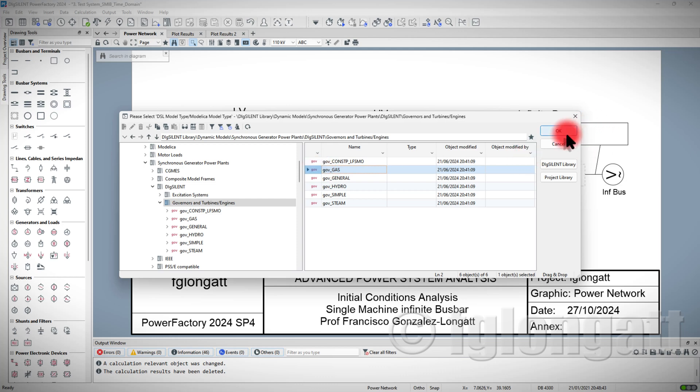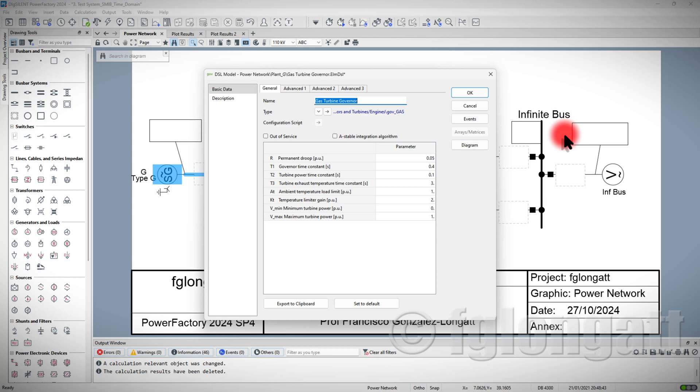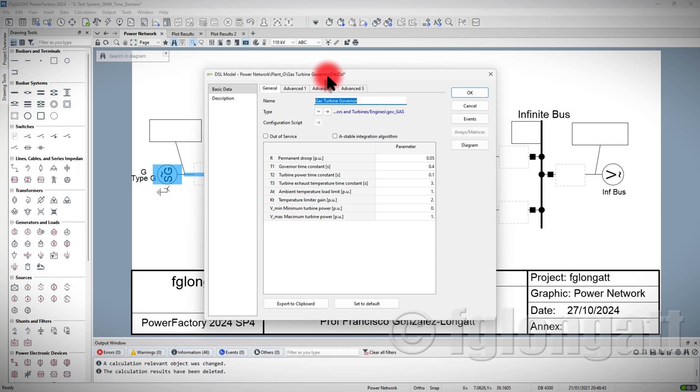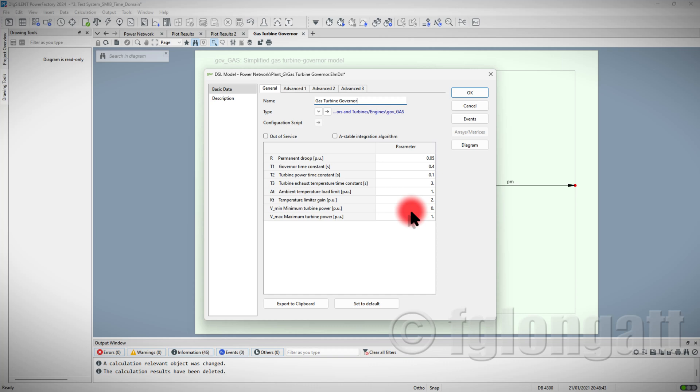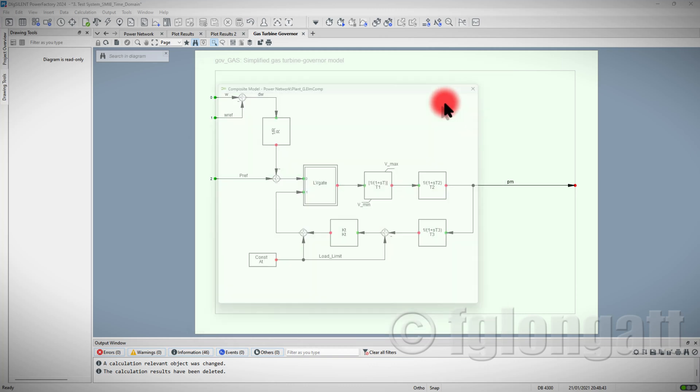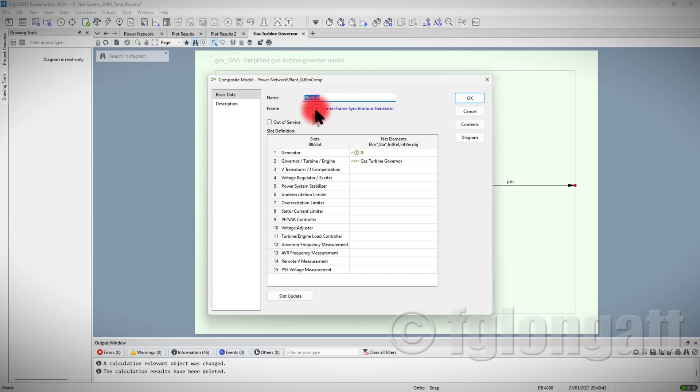Now, I select here the governor and PowerFactory is doing a lot of things behind the screen for you. One of the things is that they are creating automatically this DSL model, and this DSL model is coming from a graphical representation of the governor and turbine. Here, you can see on the right-hand side, you have all the parameters of this turbine. I want to use this model and those parameters. Then, PowerFactory will create for you this composite model, and this composite model is based on this frame over here.